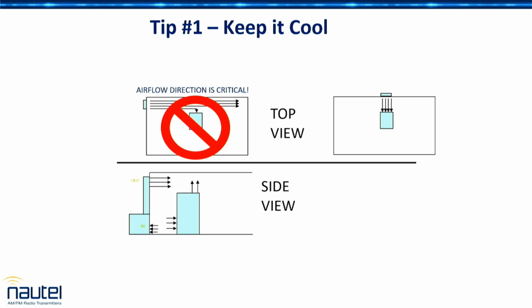Because transmitters run the cool air in down low, or in the back somewhere, or in the front, depending on the transmitter, and hot air gets shoved out the top. Well, if you've got this kind of system, you're just mixing your cool air and your hot air and doing absolutely nothing, and down here you're pulling the cool air away from the transmitter, so again, starving the transmitter for airflow.